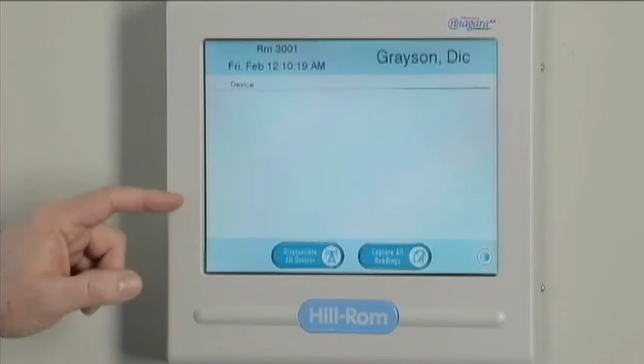It also identifies the room number and the date and time and a list of devices that are associated with this particular hub. Currently, none are associated. The beacon is just identifying the room and sending out a combination of signals, an RF signal and an ultrasonic signal. MDAs, on the other hand, go on medical devices, and they are searching for a hub to actually associate or bind with. So they're being rolled around in the hallways, brought into rooms, and as they come into the room, they are looking for signals from beacons that are identifying the room identification.